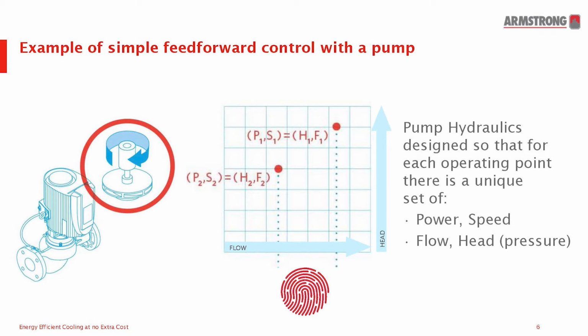We've used feed-forward control, and as a simple example of how that gets deployed, I'm going to use a product in a two-dimensional space. It's not because we manufacture pumps, it's just because a pump really is a two-dimensional space. And what we've done with our hydraulics and our pumps, we've designed them so that for the amount of flow going through the pump and the amount of pressure across the suction and the discharge of the pump, there's a unique combination.